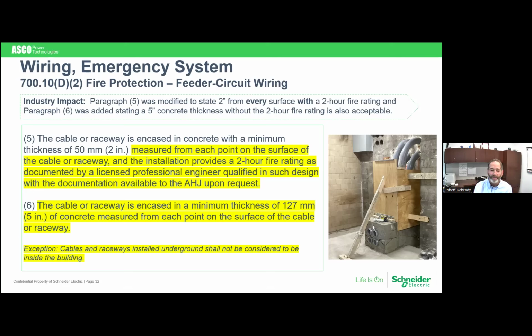If you don't want to do that, then you have to go down to number 6 here, and you have to encase that conduit or wiring within 5 inches of concrete, which, funny enough, if you look at the photograph off to the right here, this looks like conduit covered in 5 inches of concrete, and they got the upper portion here all formed up to pour in more concrete to cover the vertical conduit that's going up. So pretty interesting, pretty important.